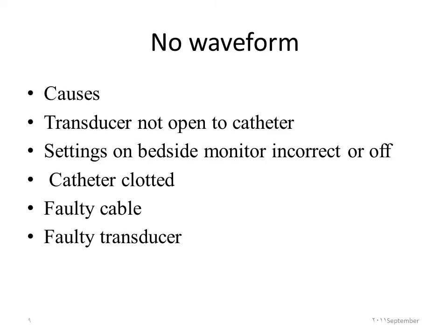If no waveform appears on the monitor, the causes could be: the transducer is not open to the catheter, and therefore the transducer will not receive the physiologic signal from the patient and will not be able to transmit this physiologic signal to the monitor. The setting on the bedside monitor is incorrect or off.